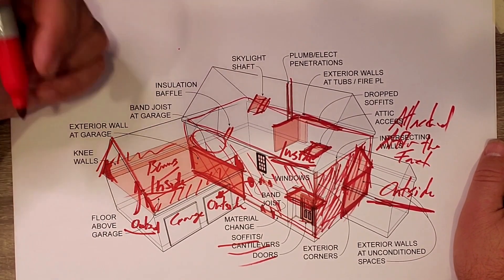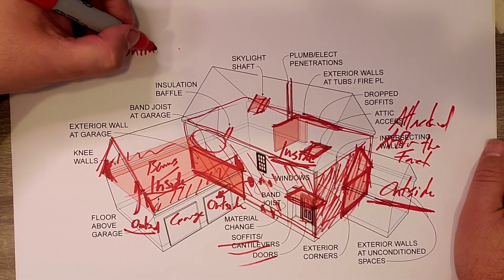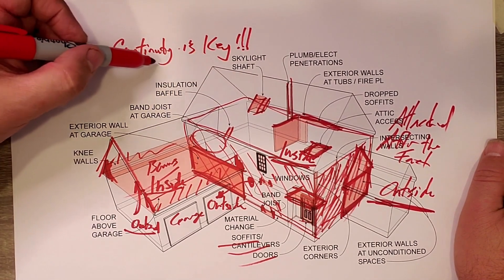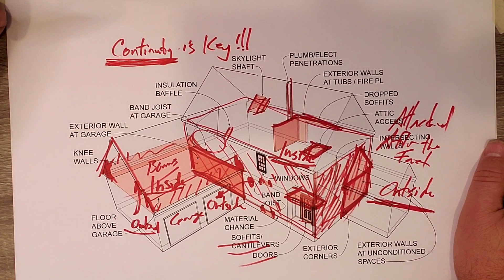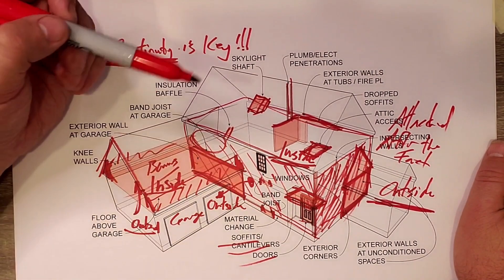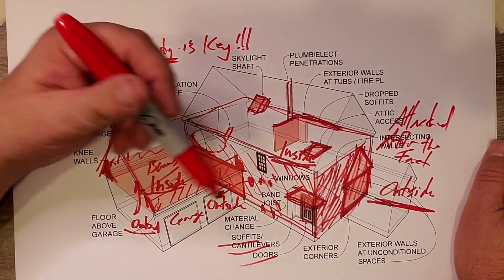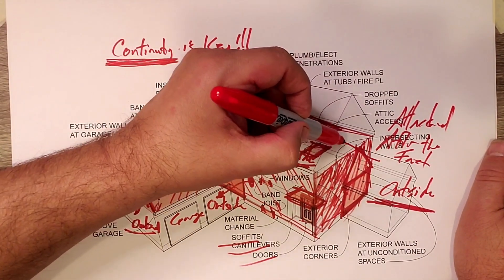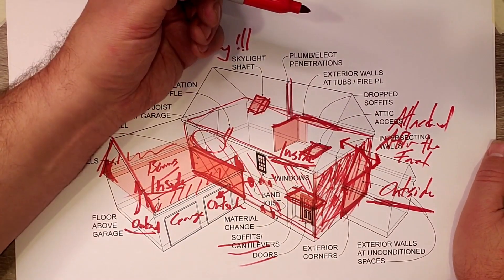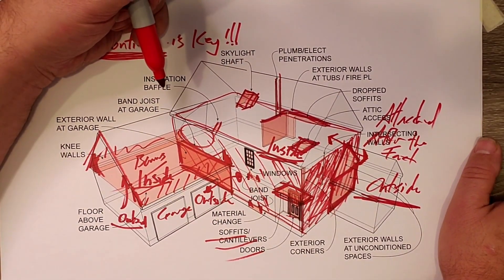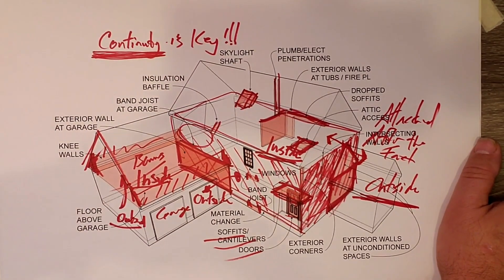The things that really matter when it comes to an air barrier: continuity is key — that's the number one thing. Air barriers rely on continuity; there is no way around that. The more continuous we make it, the better our blower door numbers become, the more energy efficient the house gets. A lot of people think it's all about energy, but it isn't. If I can make my walls basically hermetically sealed, then I don't get anything moving across the walls uncontrollably — meaning I don't get air streams that moisture can jump on and deliver moisture-laden air to cold surfaces that would condense inside the wall and create problems.